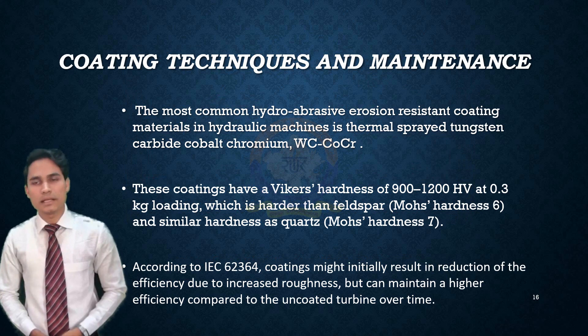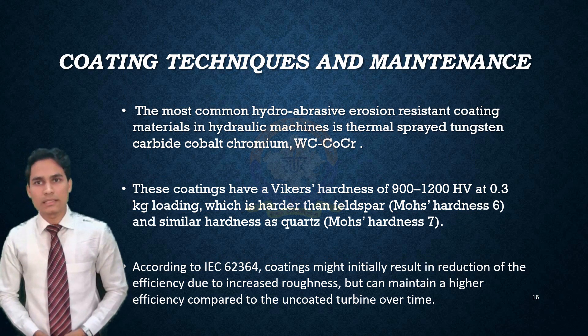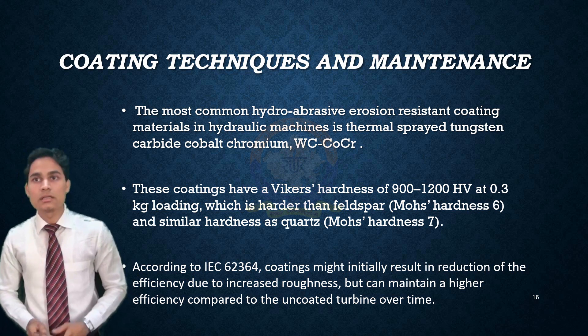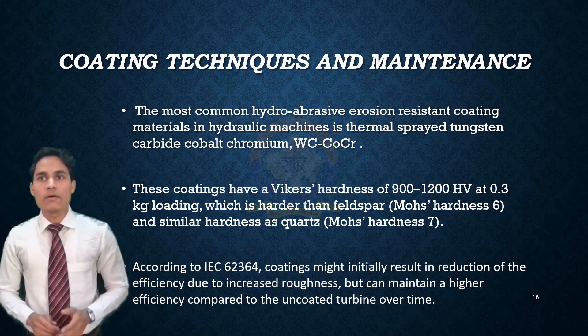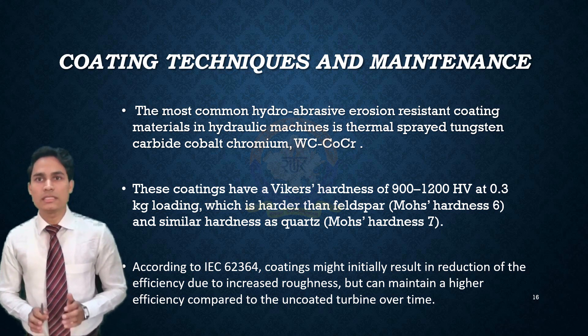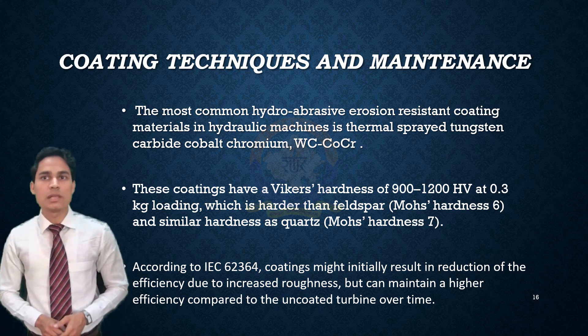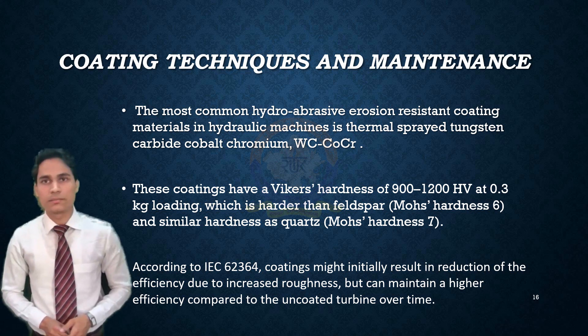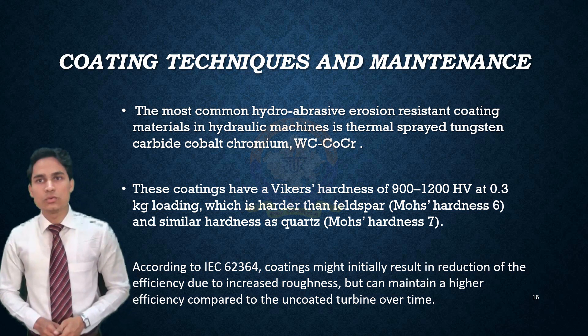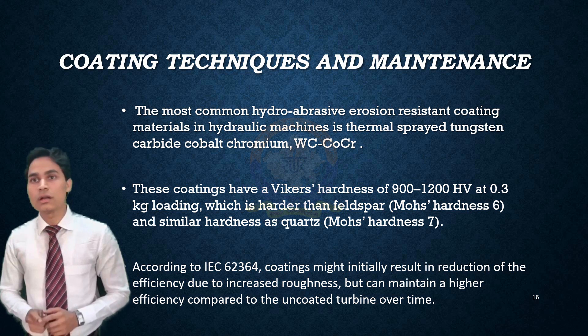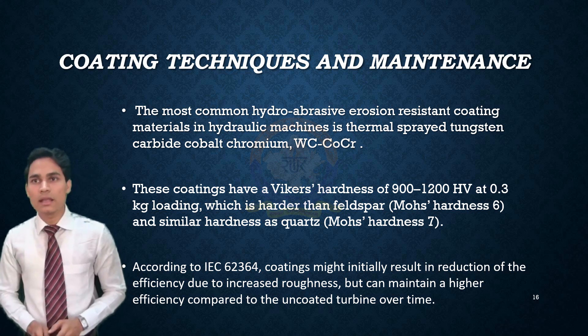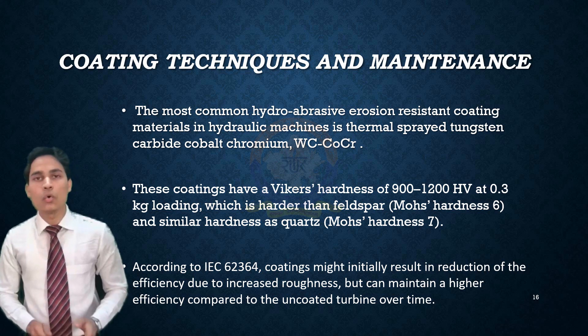This image shows the leakage flow and vortex core through the clearance gap. Coating techniques and maintenance. The most common hydro-abrasive erosion resistance coating material in hydraulic machines is the thermal spray tungsten carbide coating. These coatings have a Vickers hardness of 900–1200 HV at 0.3 kg loading, which is harder than feldspar and of similar hardness to quartz. According to IEC 62364, coating might initially result in a reduction of efficiency due to roughness, but can maintain higher efficiency compared to an uncoated turbine over time.